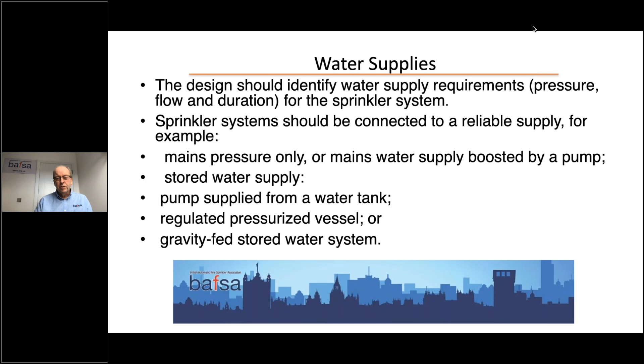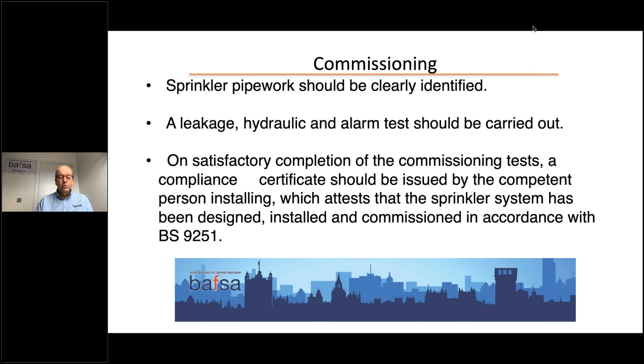Thank you. Commissioning: the sprinkler pipework should all be clearly identified so that everyone knows that that water pipe is for the sprinkler system, it is not for drinking water. A leakage, hydraulic and alarm test should be carried out when the sprinkler system has been installed. And on satisfactory completion of the commissioning tests, a compliance certificate should be issued by the competent person installing the system. This shows that the sprinkler system has been designed, installed and commissioned in accordance with BS 9251.